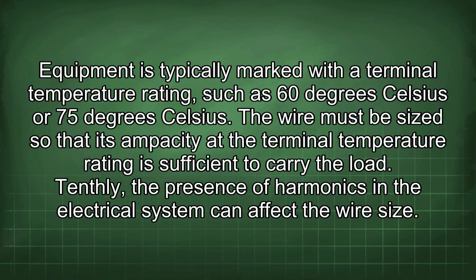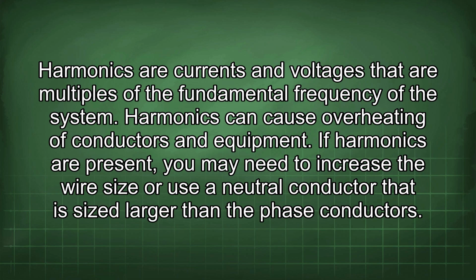Equipment is typically marked with a terminal temperature rating such as 60 degrees Celsius or 75 degrees Celsius. The wire must be sized so that its ampacity at the terminal temperature rating is sufficient to carry the load. Tenthly, the presence of harmonics in the electrical system can affect the wire size. Harmonics are currents and voltages that are multiples of the fundamental frequency of the system. Harmonics can cause overheating of conductors and equipment. If harmonics are present, you may need to increase the wire size or use a neutral conductor that is sized larger than the phase conductors.